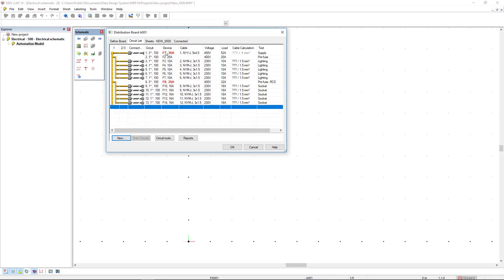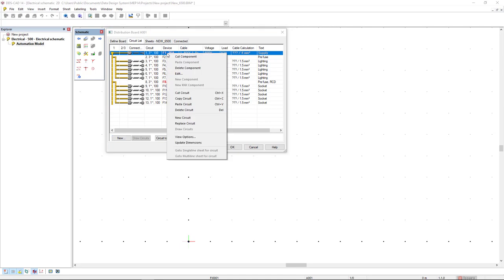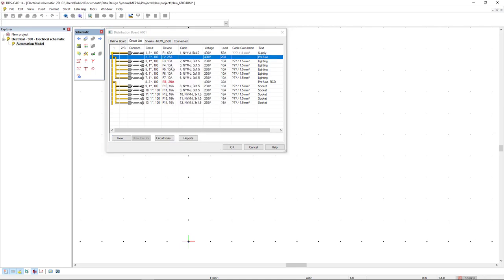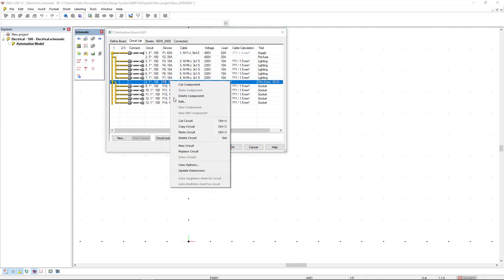We can see in the device column that the current for the supply and for the second protective overload protection is in red, so it's under dimensioned. I can select this circuit, right mouse click and select the option update dimensions. It automatically redimensions the current. And I will do the same here.